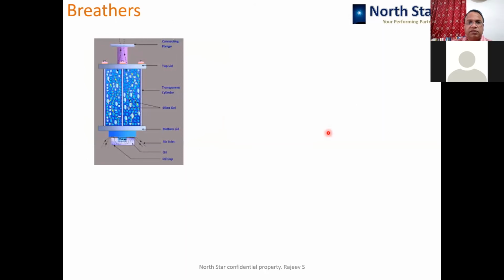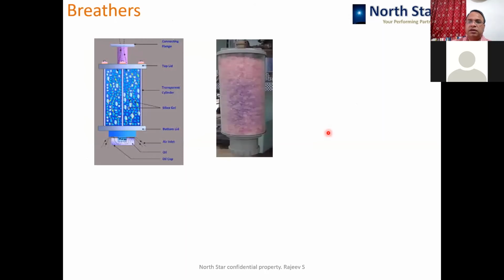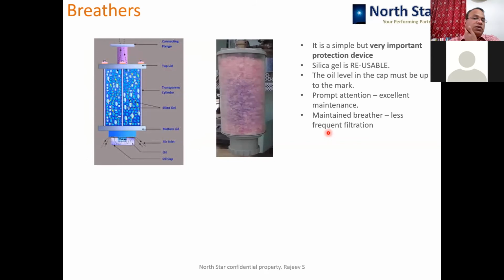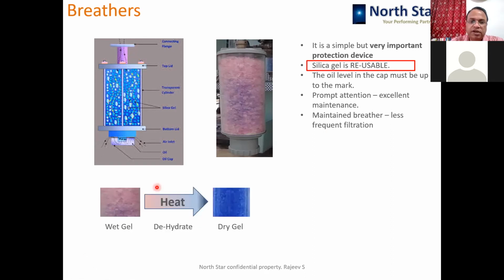Now coming to breathers, I love this device. It is such a simple arrangement, but if maintained properly, it can save your transformer from the effect of excessive moisture. But the only thing is that during routine activities, it is not maintained, and normally you find the silica gel is pink in color. That means it is moist. The moisture has gone into it. Okay, so it is reusable. So you have a wet gel, you heat it by some means, and you will get blue gel again, which is dry gel.